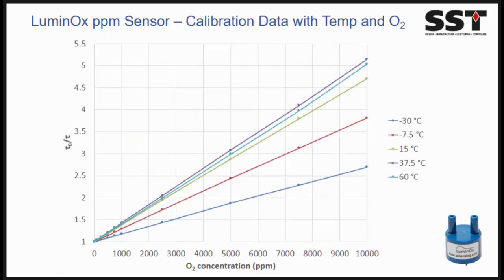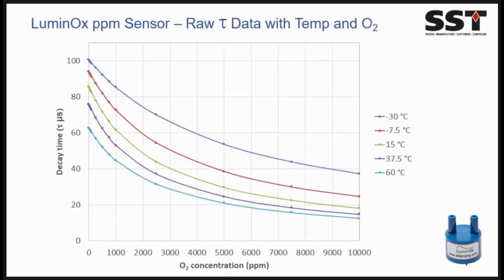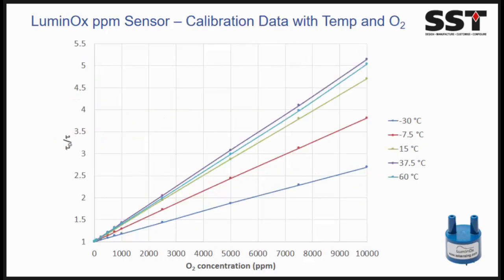You can see that the sensitivity at 60 Celsius changes slightly, but we can characterize that from the decay time here. This is just a difference in the solubility of the oxygen passing through into the materials at that temperature. This makes calibration so much easier, that we have a nice linear correlation over the full range from -30 Celsius to 60 Celsius and 0 to 10,000 ppm.